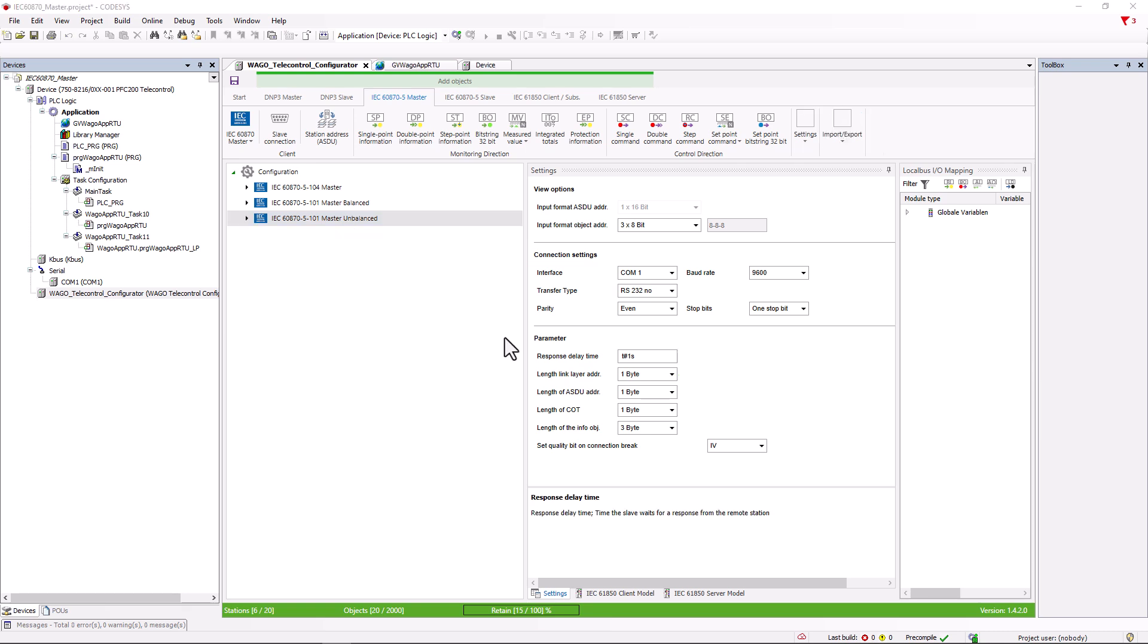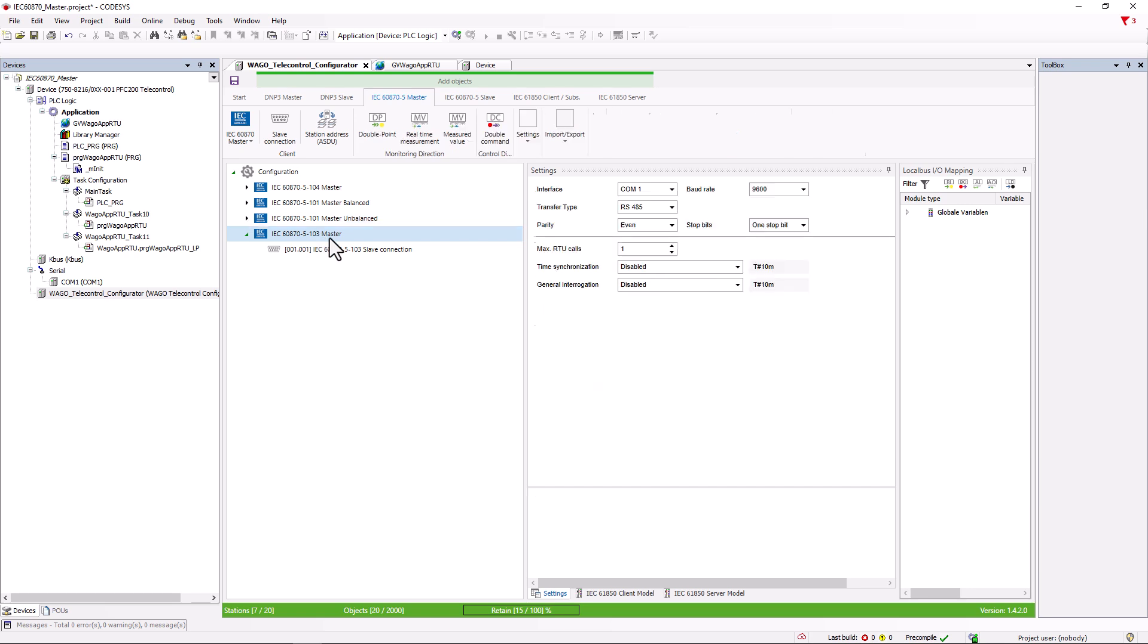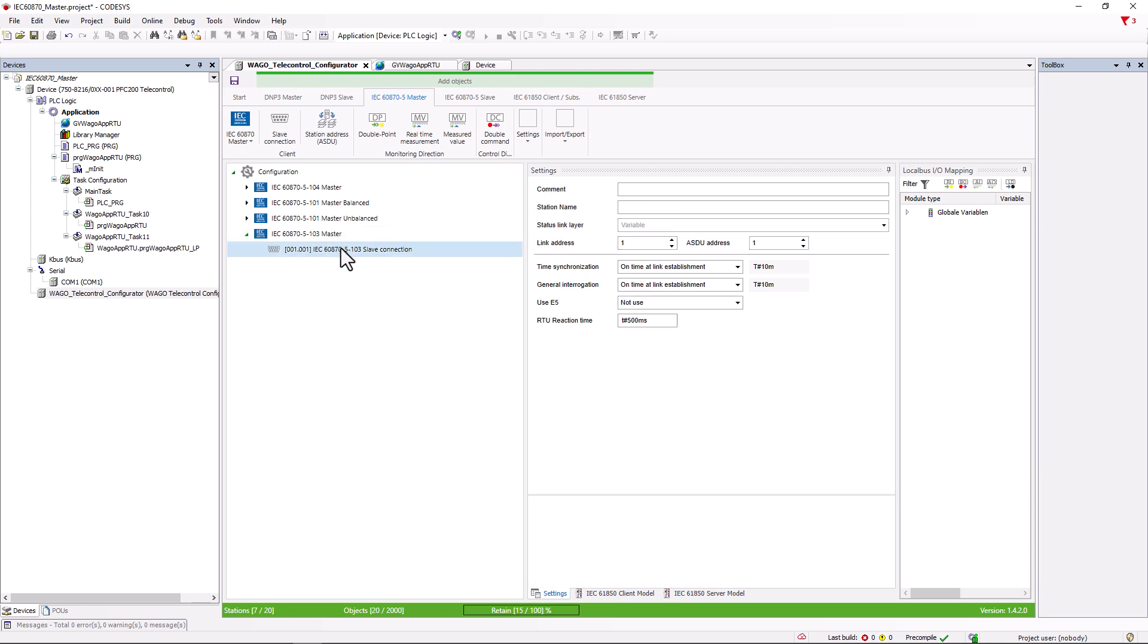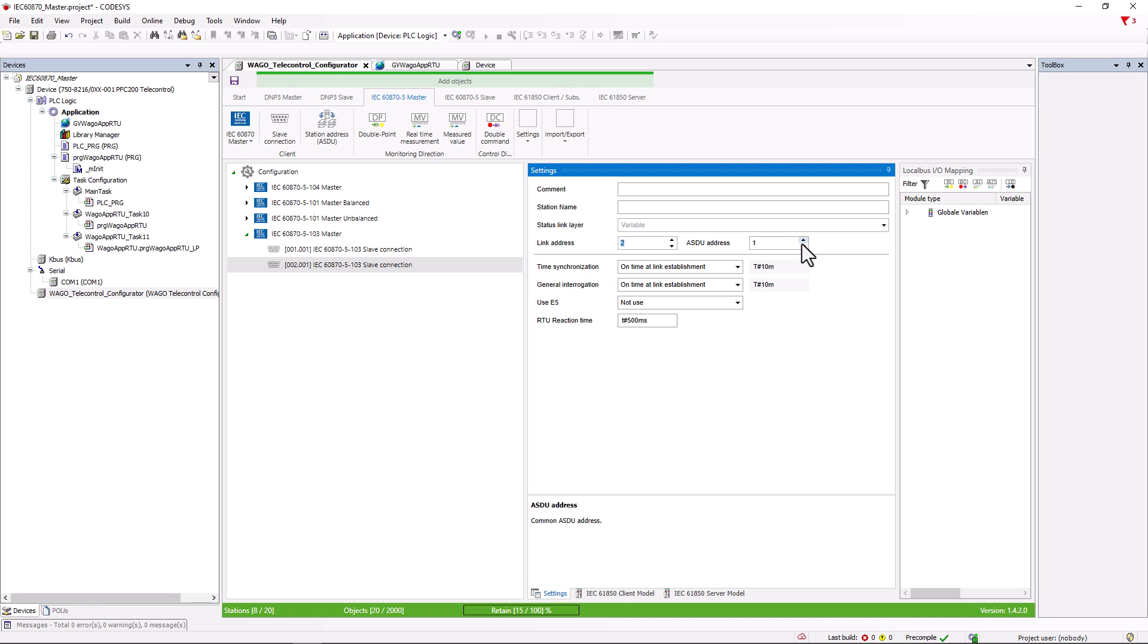Serial Master 103. The 103 protocol is specifically designed to connect protection devices and therefore has more limited options. This is reflected in the General settings and in the settings for the Slave connection. As protection devices are often set up in a line structure, it has become established that the link address and the ASDU address are assigned equal. If further slave connections are added, the link address and the ASDU address would always be assigned equal.